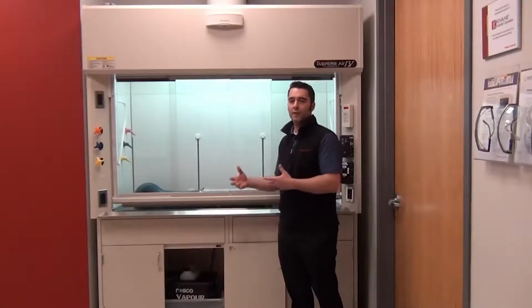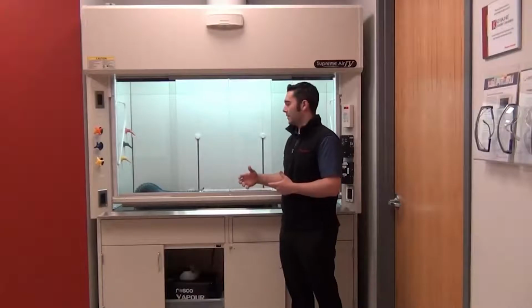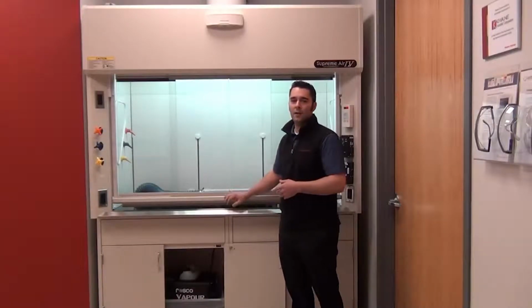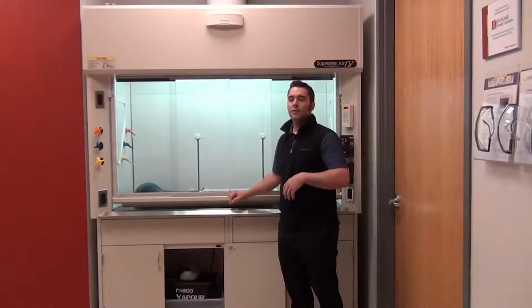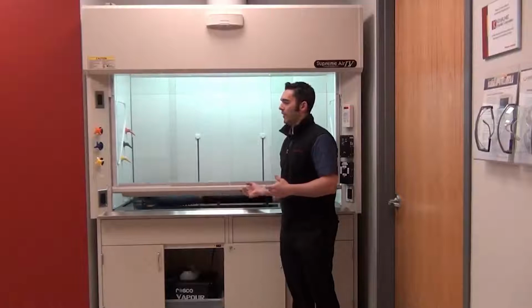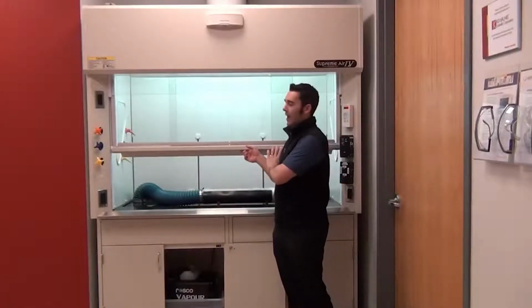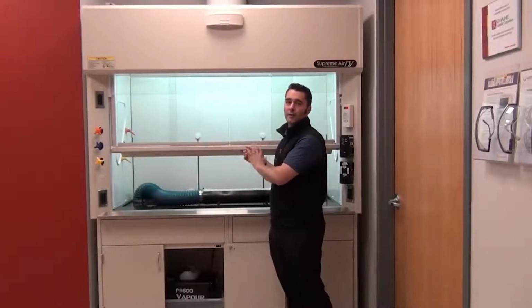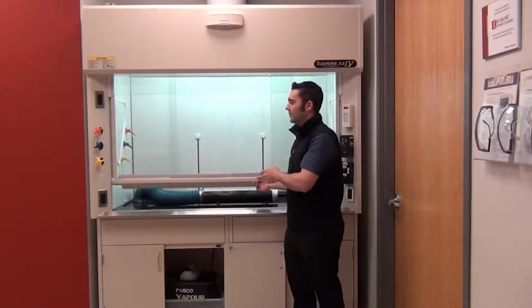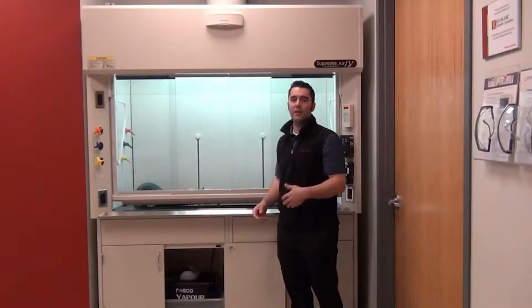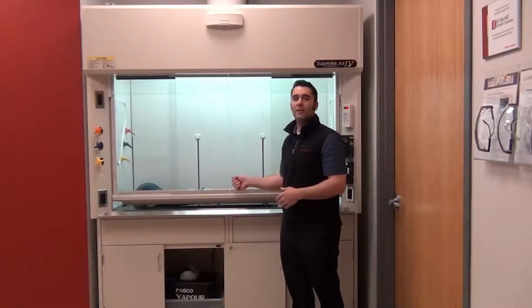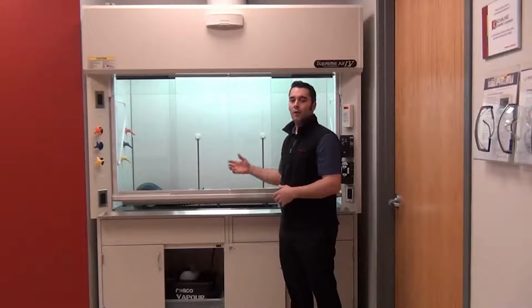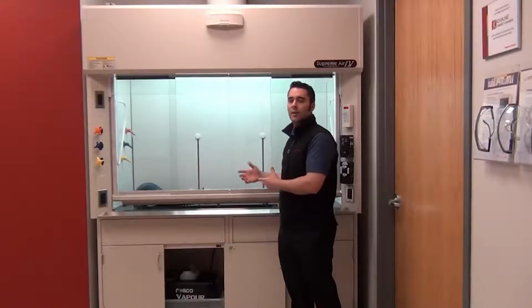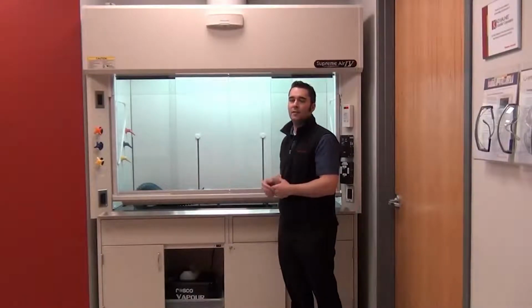Phoenix Controls Venturi valve on top of the fume hood, is to guarantee the safety of the occupants that are using this fume hood. So the fume hood has to adhere to certain standards that allow a certain face velocity of air, which is an average amount of air going across the front of the fume hood at a given velocity at all times. It also has to maintain a certain speed of response to guarantee that as I'm moving these panes around, my valve can track where the hood is going at all times to make sure that I'm maintaining safe containment inside of the fume hood.